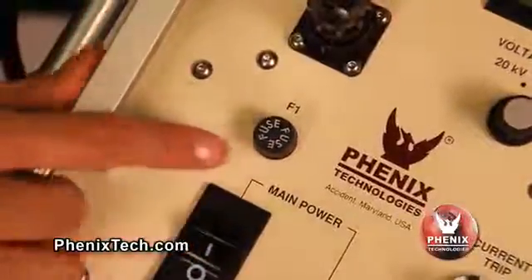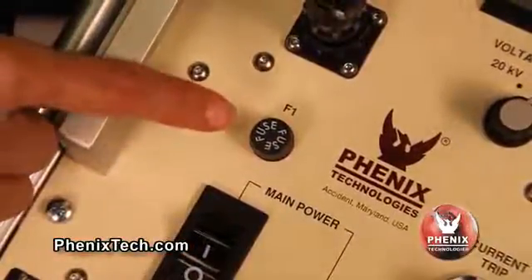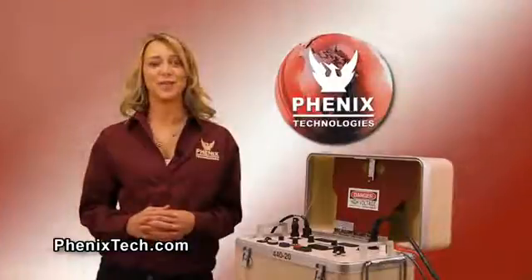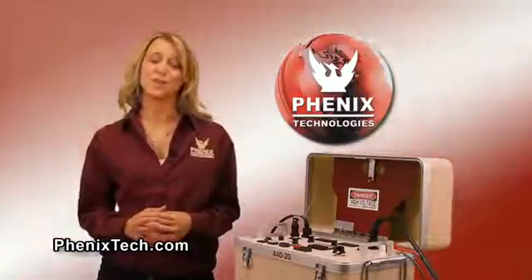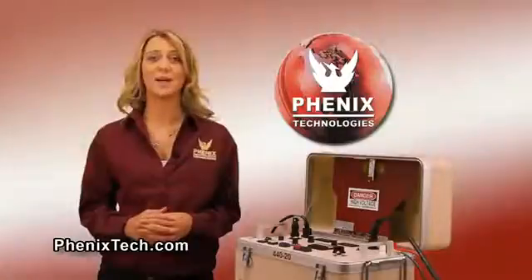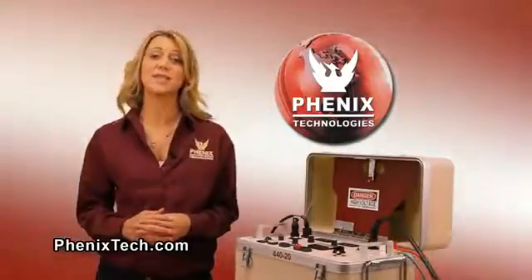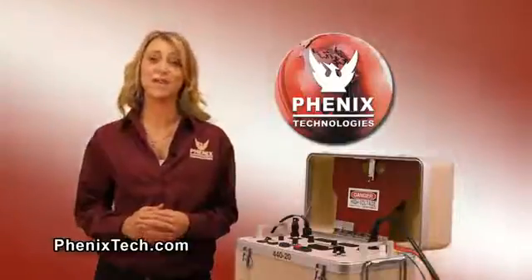Our high pots have a built-in discharge circuit. This feature allows any residual charge that may remain on the test object to discharge after the high pot is turned off. The fuse is sized to protect the control power circuit, and the thermal overload protects the high voltage transformer. Thank you for watching this video. Please go to our website for additional information regarding our portable DC high pots and the many other high voltage and high current test sets manufactured by Phenix Technologies.